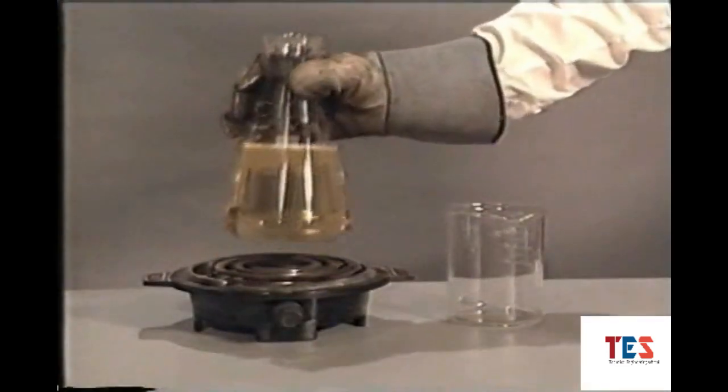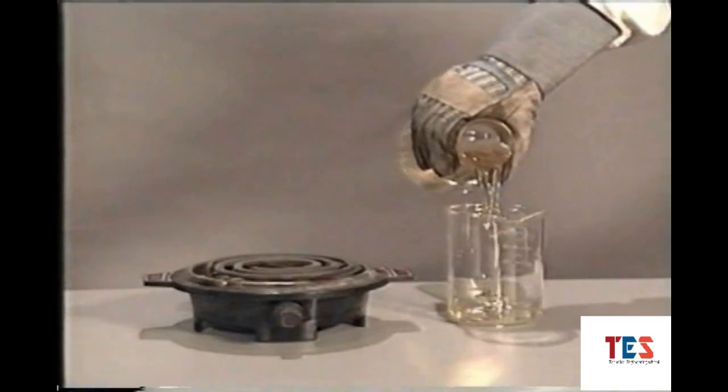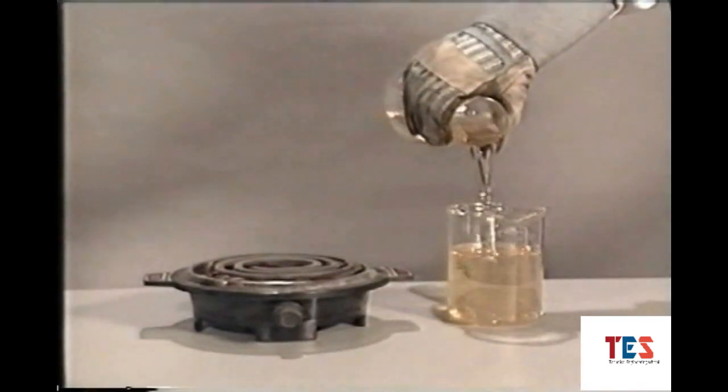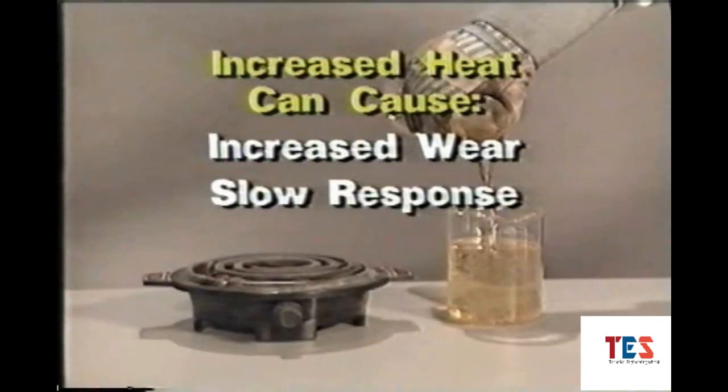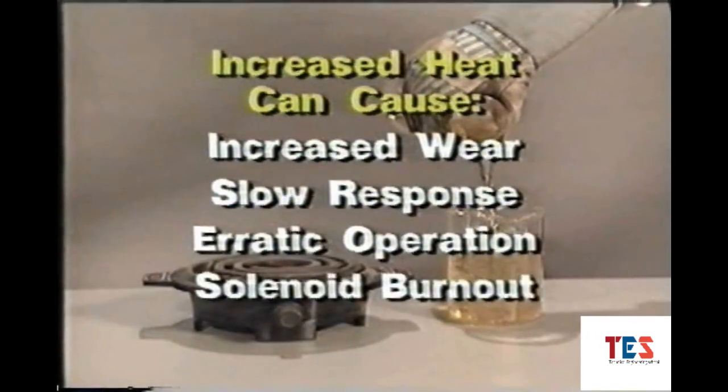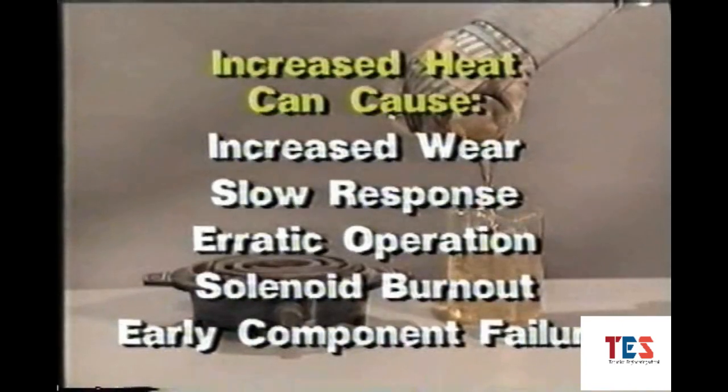If the fluid gets too hot, it will lose viscosity and may not provide adequate lubrication. This can lead to increased wear, slow response, erratic operation, solenoid burnout, and early component failure.